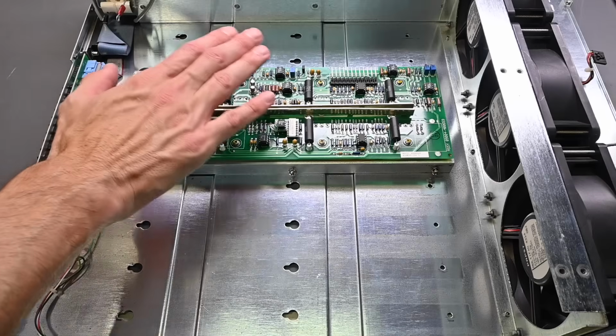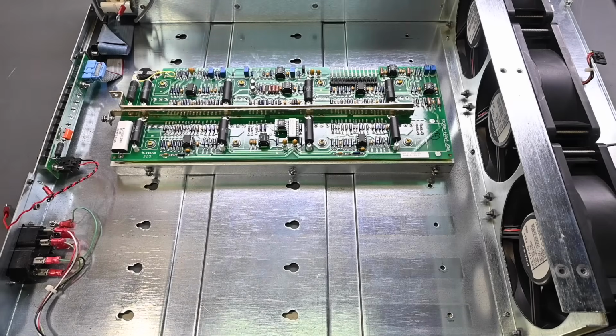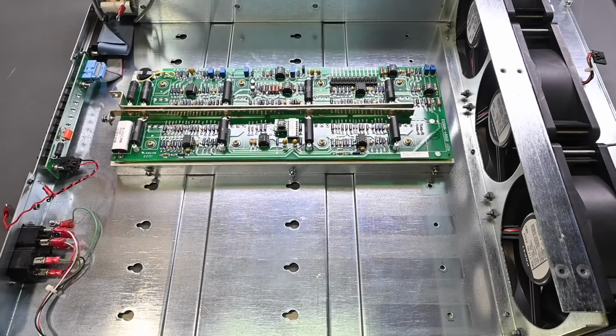So all of these modules are operated in parallel, and they're always connected in parallel at all times, and all 9 modules are operating together all the time. So if the electronic load is dissipating 1 watt or 2,000 watts, it doesn't matter. All of the modules are sharing the load, no matter how large or small it is. The 9 modules at 2,000 watts, just take 2,000 divided by 9, you're asking each module as a maximum to dissipate 222.22 watts. So you can imagine these get quite warm, but of course with the air blowing over them, it's dissipating that off as the heat. But again, this does get quite hot in operation.